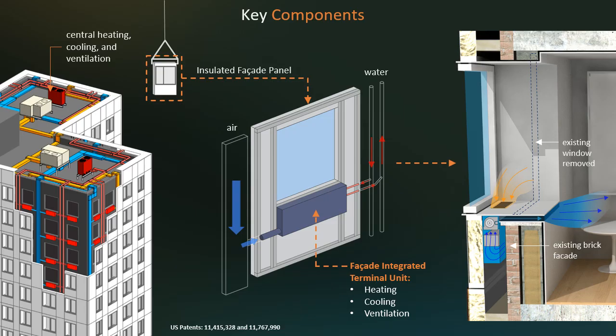They then connect to the facade integrated terminal unit, which basically is a fan coil that will help provide the heating, cooling, as well as ventilation to that particular apartment. Every occupiable space can get its own facade integrated terminal unit, essentially allowing for individual control. The facade integrated terminal unit is also a sensible only unit in the sense that there is no condensate coming out. All the latent load is taken care of by the dry and dehumidified ventilation in.